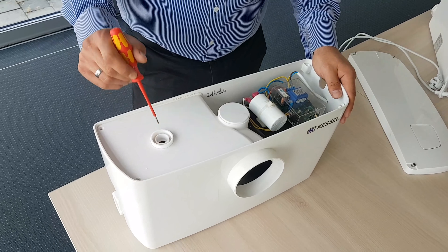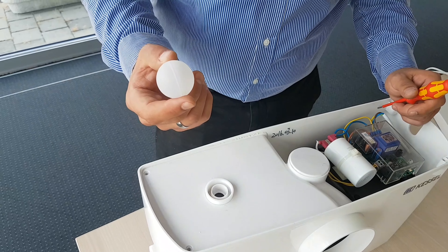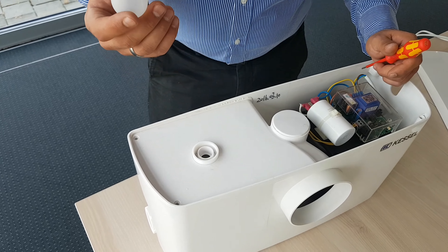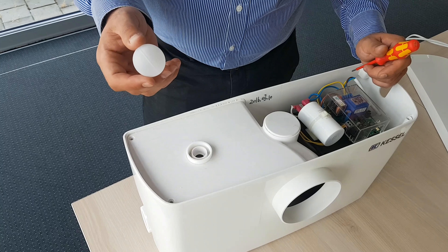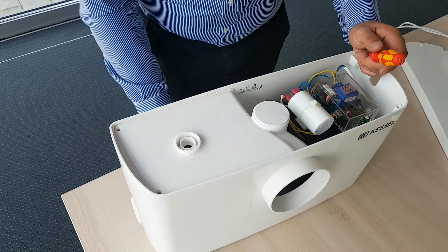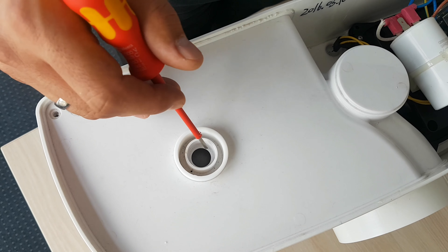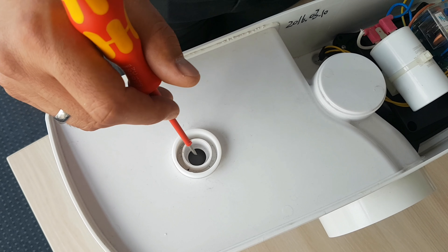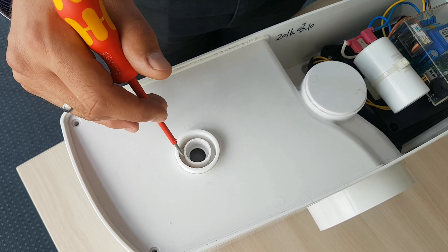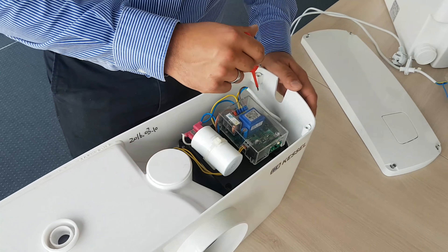Not every installation of the Minilift F works perfectly. You would also have to check if there are any issues with the lifting station. The most common thing that happens is that water comes out of the ventilation hole. The ventilation hole has a small ball that prevents water from flowing into the tank, but sometimes if the tank is very dirty, water can flow in.